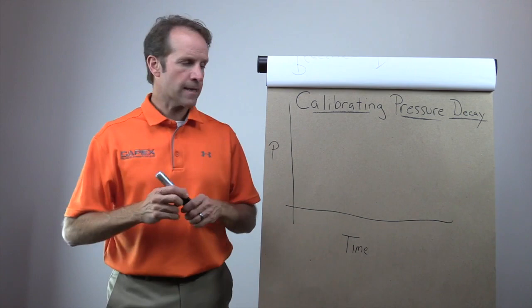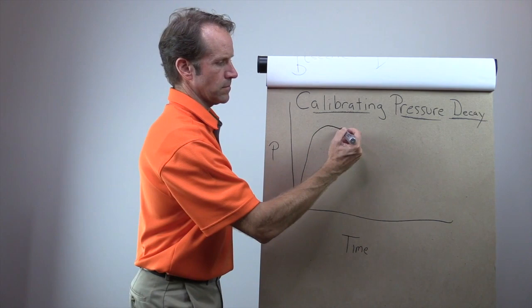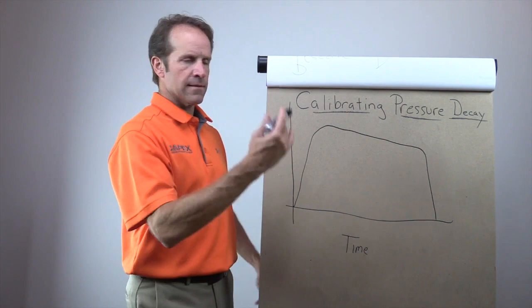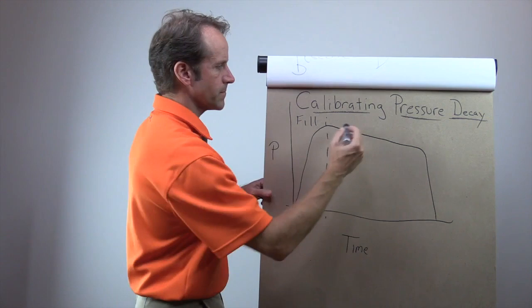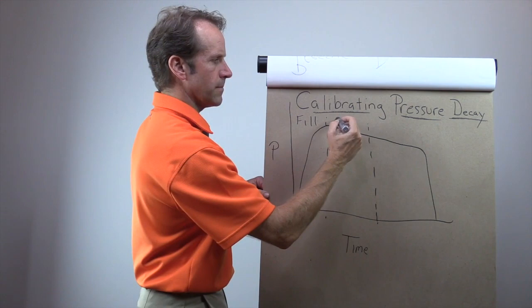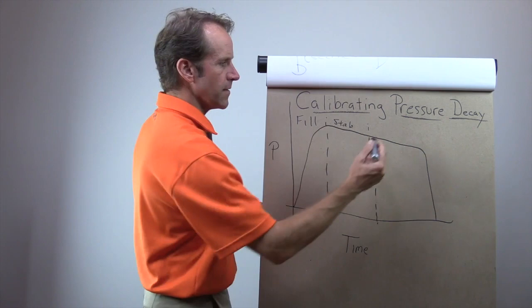You pressurize the part. And over the course of time, that is a typical test curve. Maybe it's a little steep on the pressure loss, but you get the idea. So this is going to be our fill time. This is going to be our stabilization timer. This is going to be our test timer.